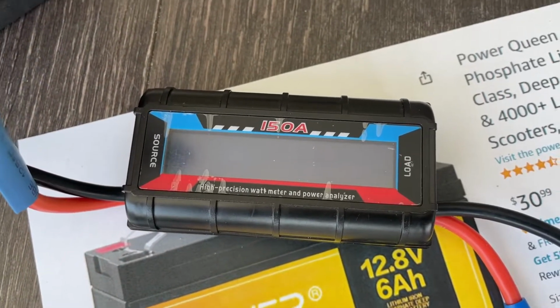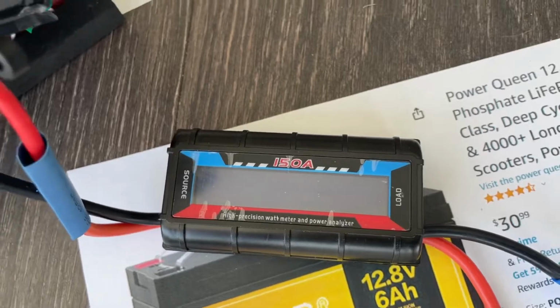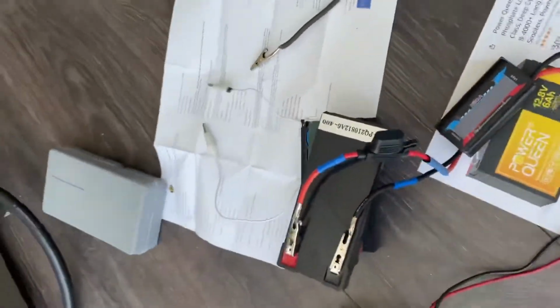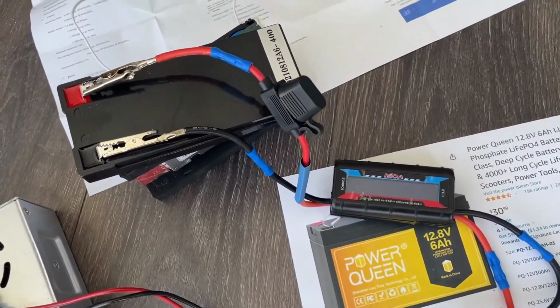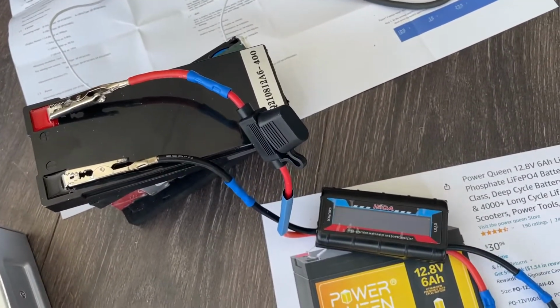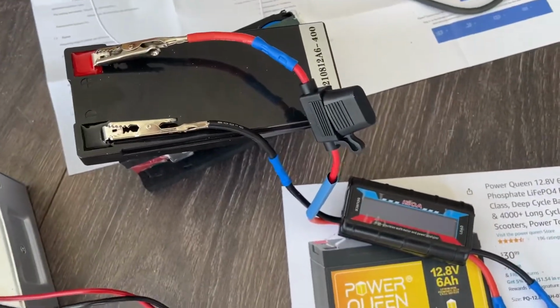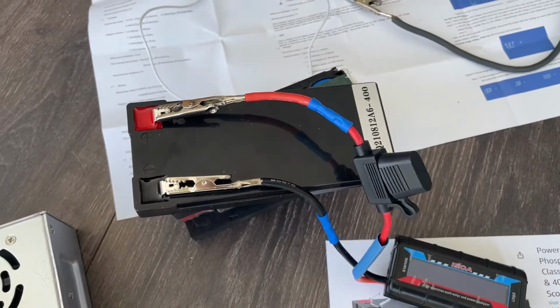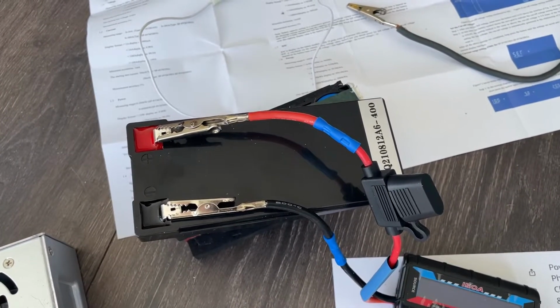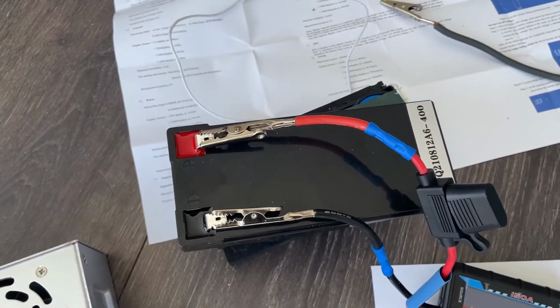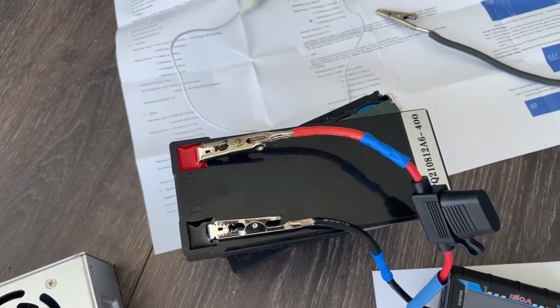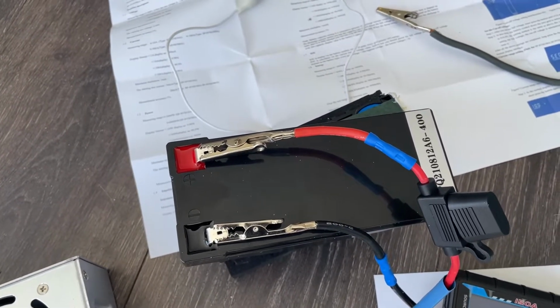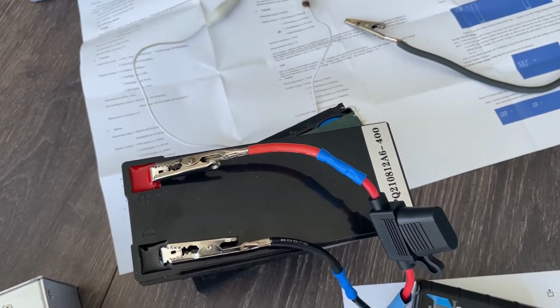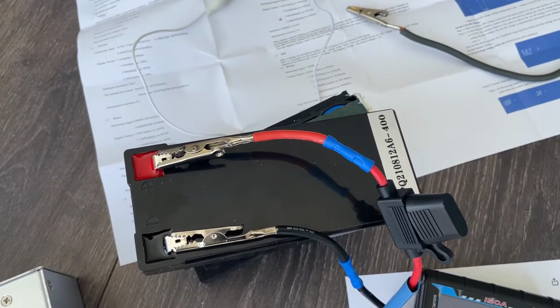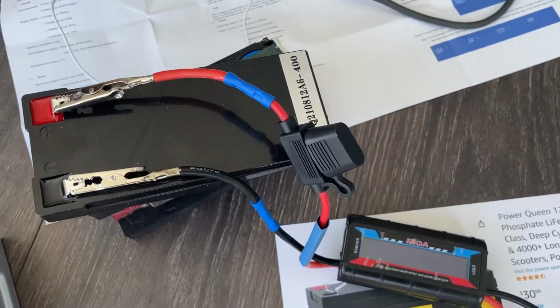Yep, I just shut it off, so that was good. Okay, so it went down to 9.5 - good thing we caught that. That's a little lower than I'd like, but it did shut off, which is good. Now, one thing I noticed: to turn the BMS back on, I had to get a voltage higher than 12 volts at the terminal - I think I used 16. I didn't test it at 13 or 14, I'll have to try that when I charge it back up. But you definitely need more than 12 volts to turn the BMS back on once it shuts off.